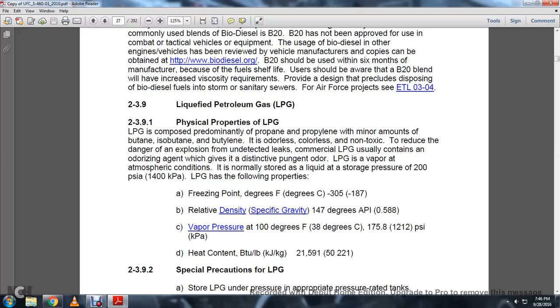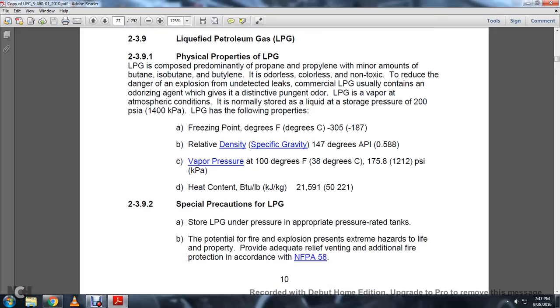Liquid petroleum gas is a vapor at atmospheric conditions. It is normally stored as a liquid at a storage pressure of 200 psi. Liquid petroleum gas has the following properties: freezing point of negative 305 degrees Fahrenheit, relative density of 147 degrees API, vapor pressure at 100 degrees Fahrenheit, heat content in BTUs per pound 21591.